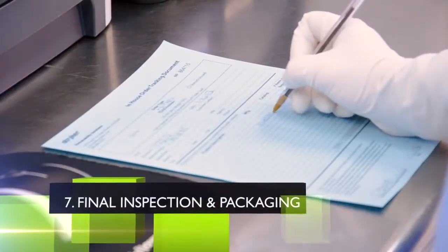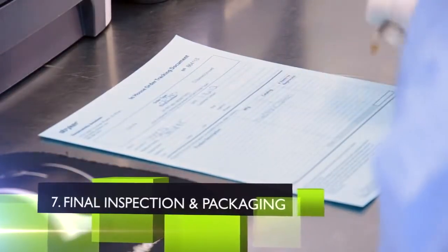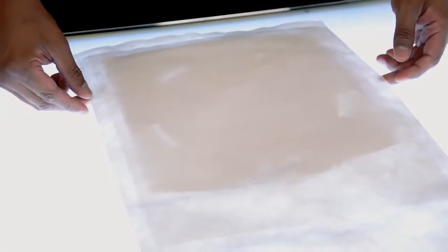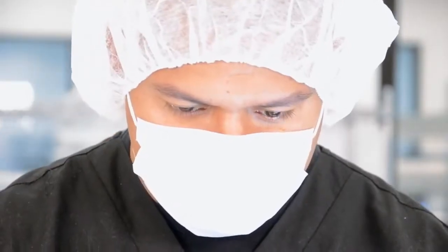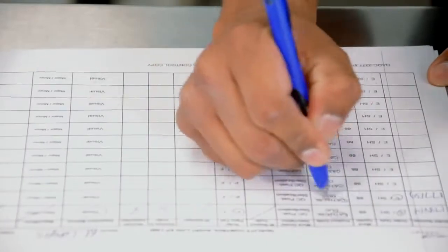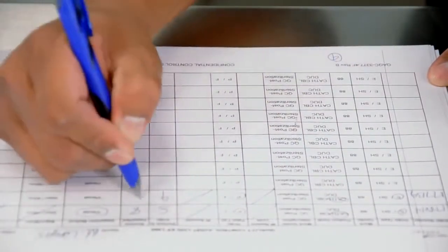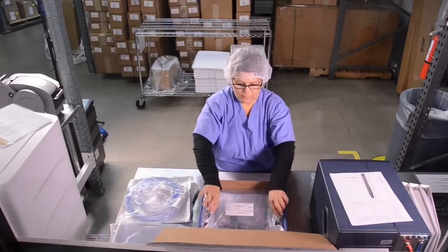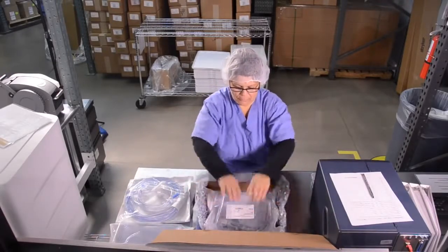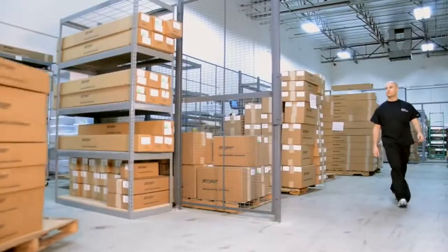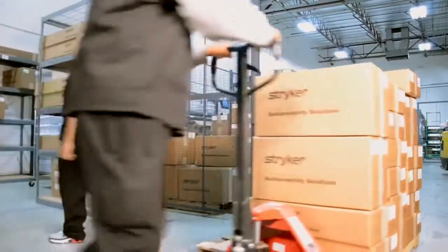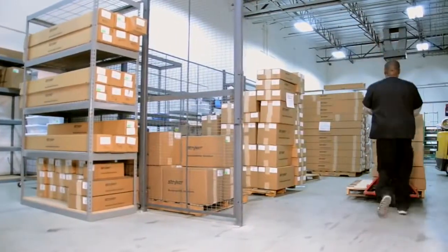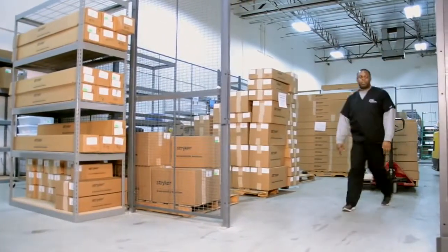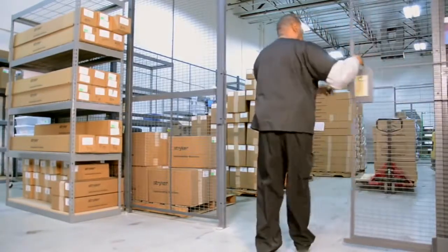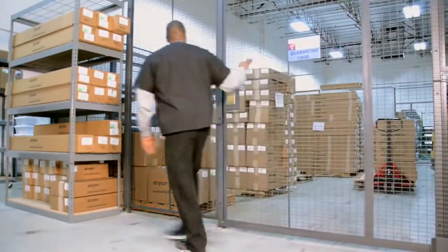The final inspection process includes examination of the paperwork to ensure that all reprocessing steps have been performed correctly. Inspectors confirm that the package seal is secure and straight and that no foreign material is inside the package. Devices are never released until sterilization is confirmed by inspectors. After final inspection, all devices are placed into their appropriate storage boxes and sent to a device quarantine area. While devices are in quarantine, Stryker's quality control personnel examine documents to ensure reprocessing has been completed correctly. No devices are released from quarantine until the quality control team confirms that all reprocessing was performed correctly.